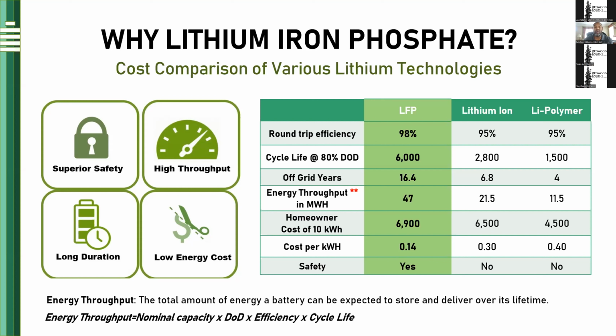Lithium batteries in general are very, very safe, so don't get that misconstrued. There may be things you see, like recently there was a battery fire. Batteries generally don't catch fire because the battery itself has a problem. What ends up happening is a failure in the battery management system, the BMS, or something happened on impact that punctured the battery. Generally batteries are a lot safer, and when comparing chemistries, you're looking at a 500 degree Celsius difference in terms of when the LFP battery chemistry would meet a failure point.